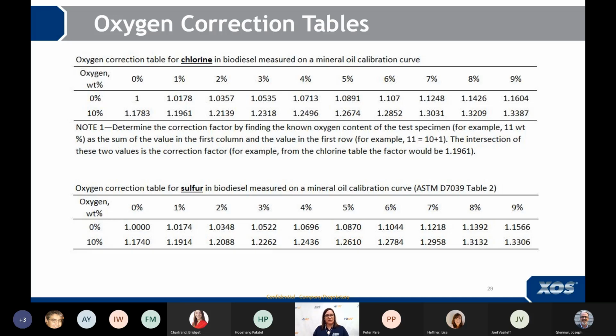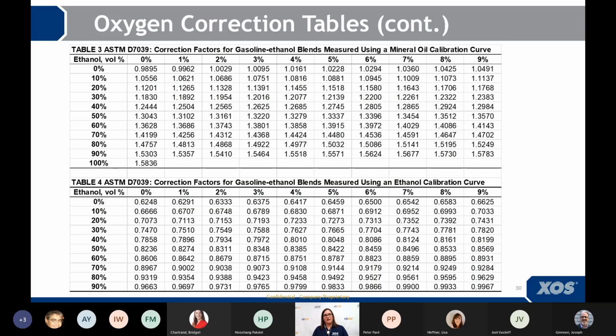Here are a couple more tables. These are in ASTM's D7039, and they are the correction factors for oxygenated samples. So if you're measuring E10 on a mineral oil calibration curve, you can look up the factor. It's 1.0556. And then the second table is if you have set up for an ethanol calibration, such as E85 or E75, if you want to measure that.